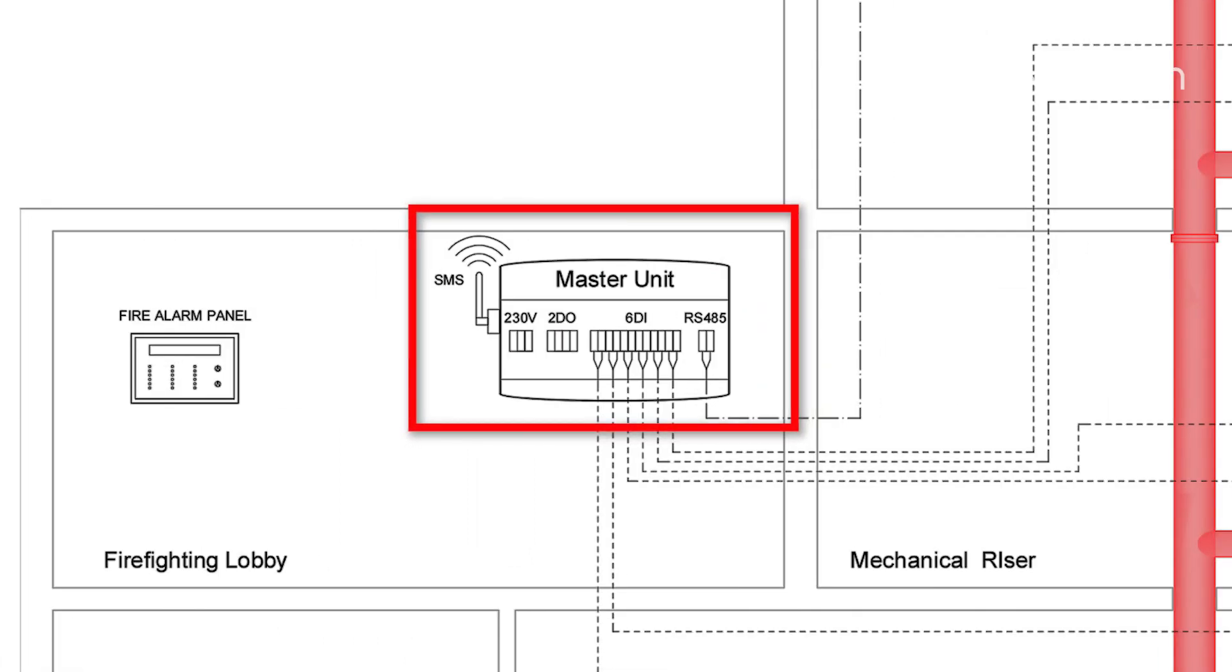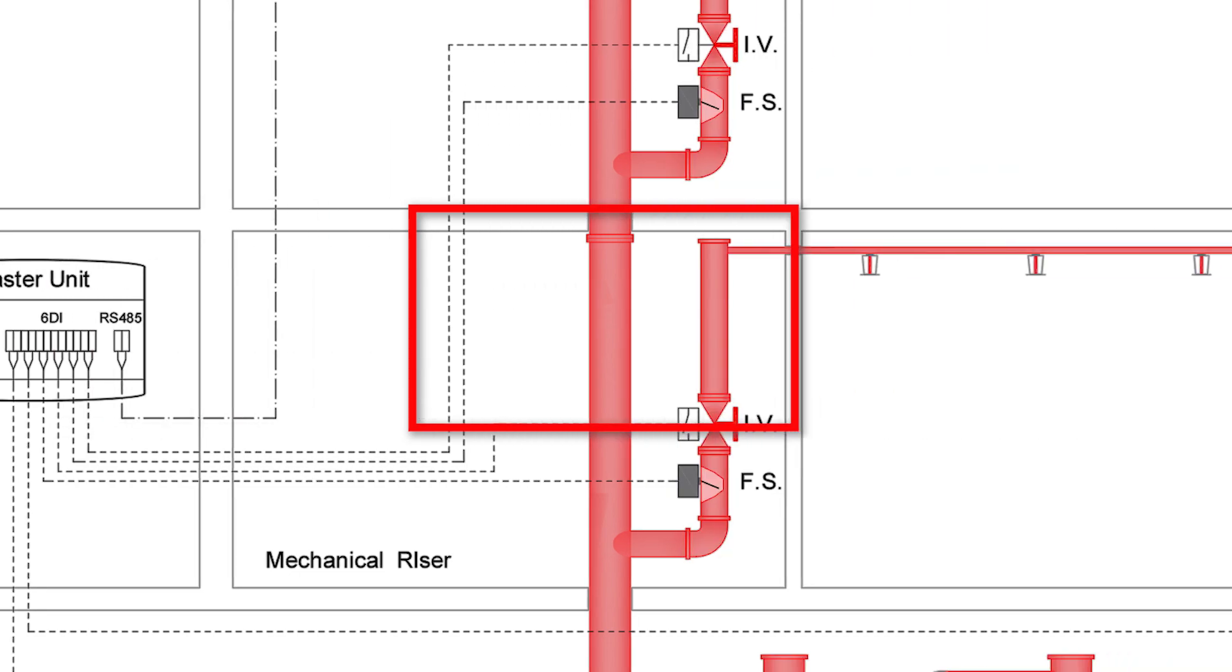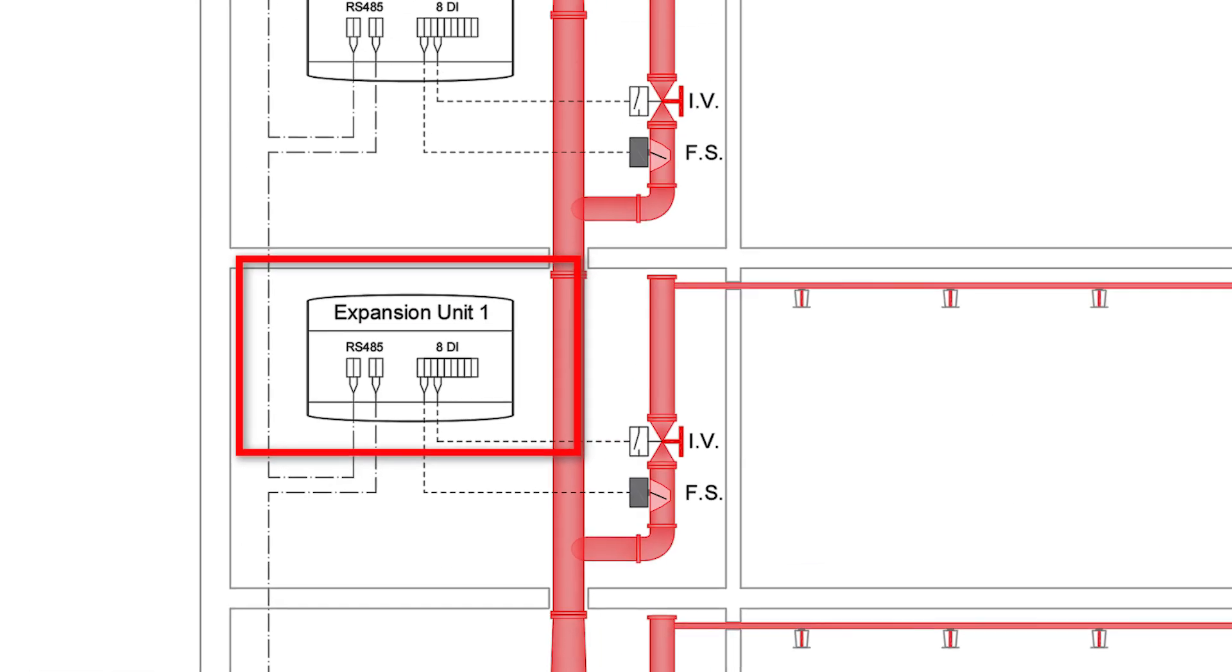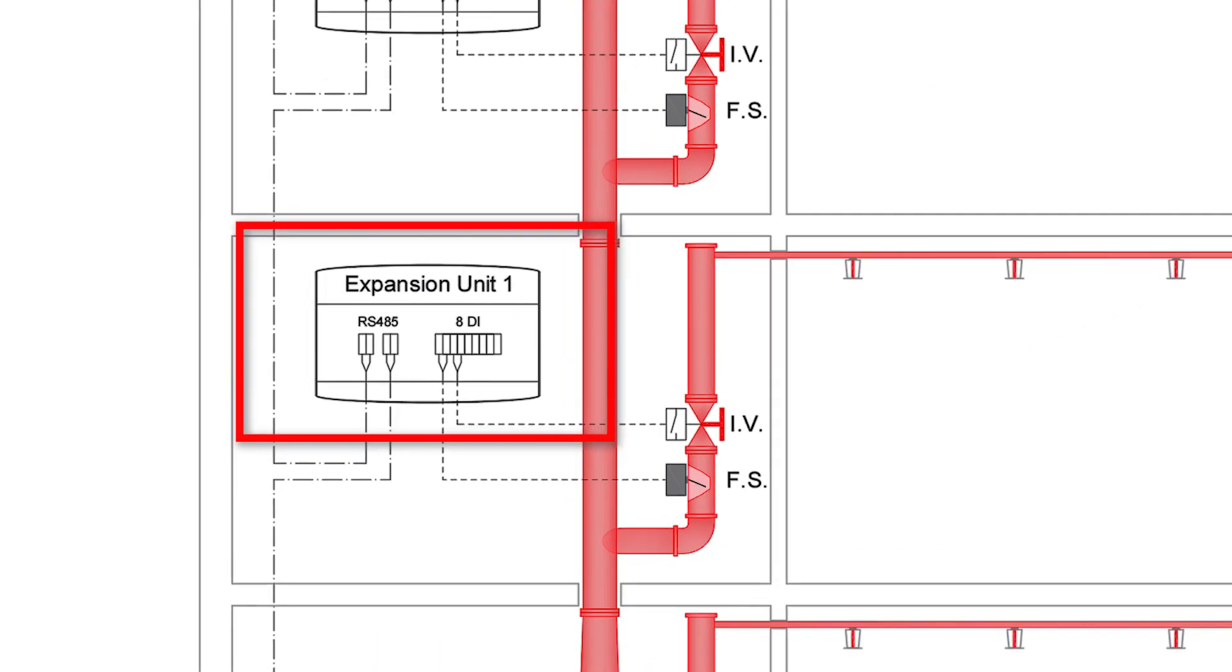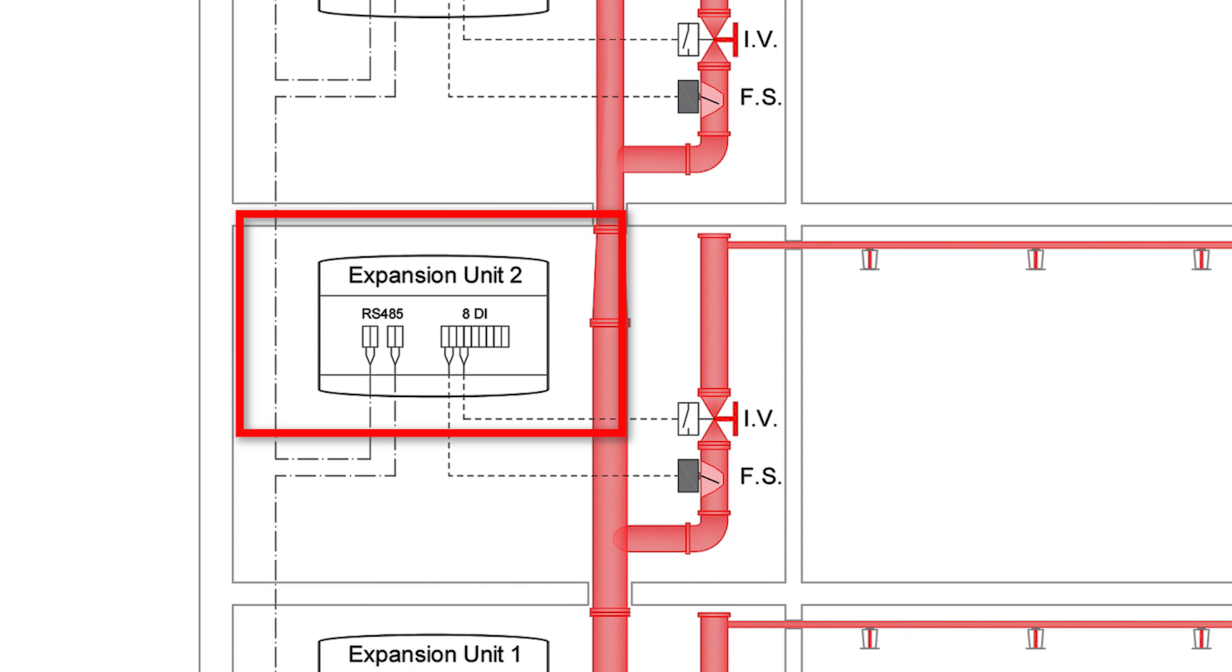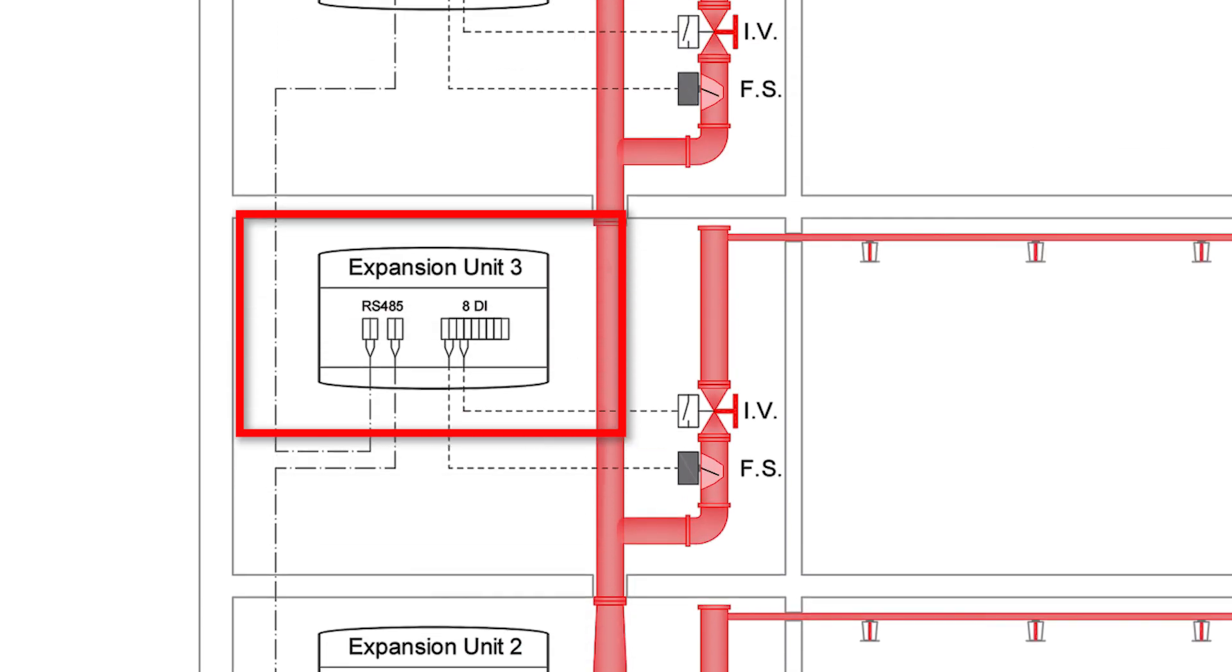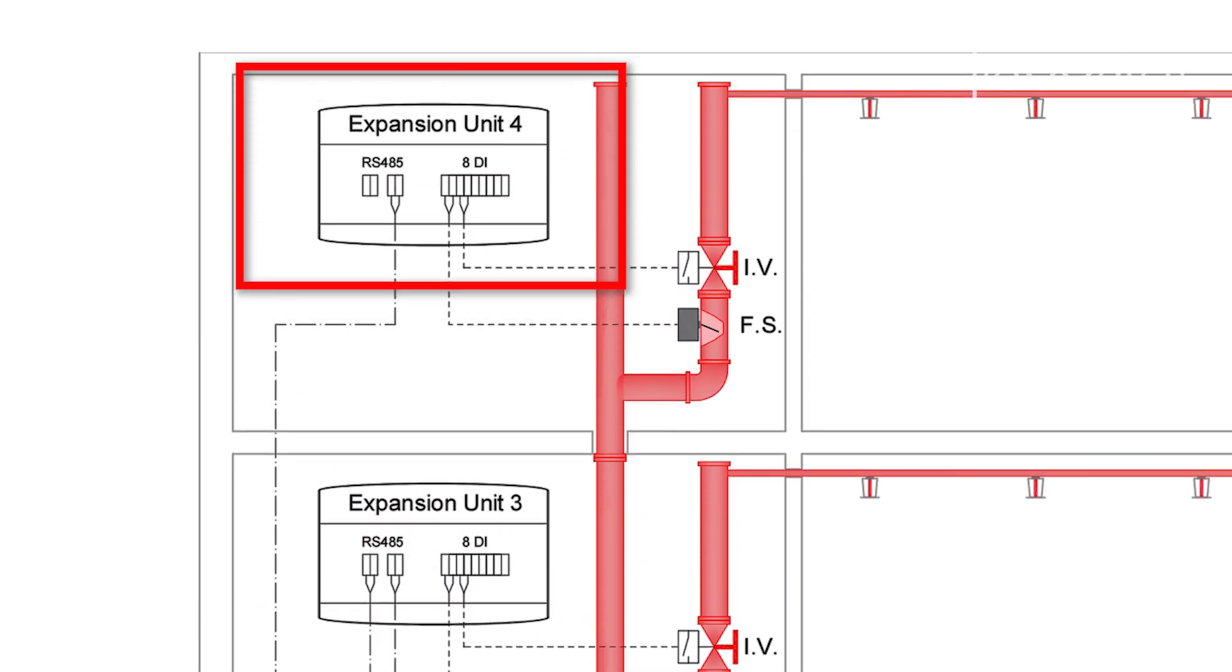If more than one expansion module is installed, then a four-core FP 200 1 millimeter cable is run from the first expansion to the second, and then the second to the third, and so on to form a daisy chain from the master to each expansion module.